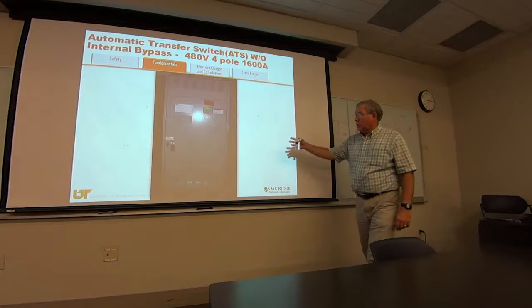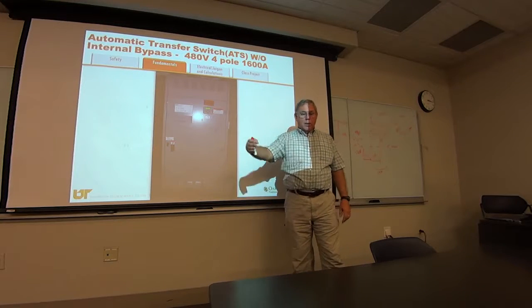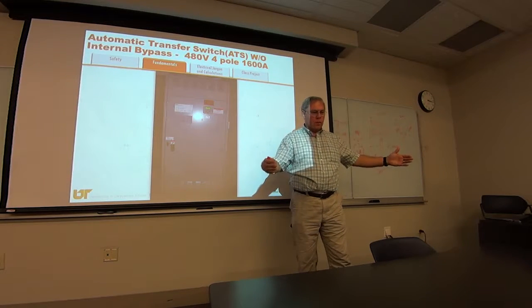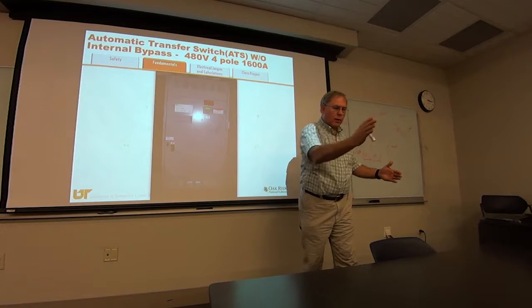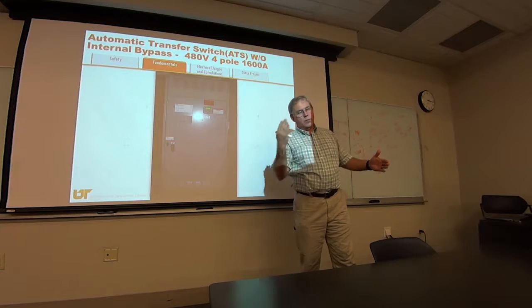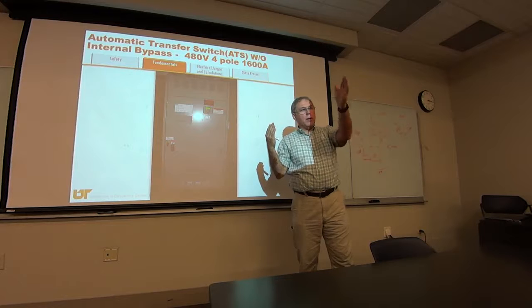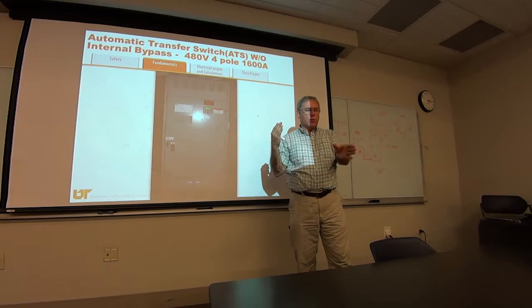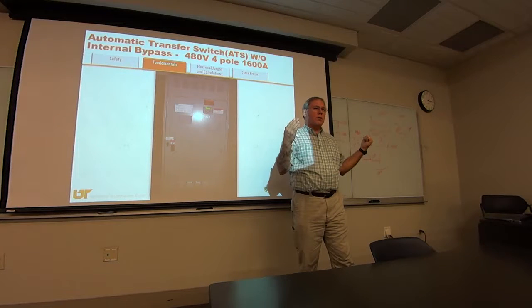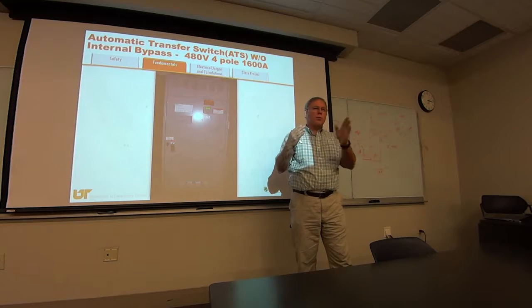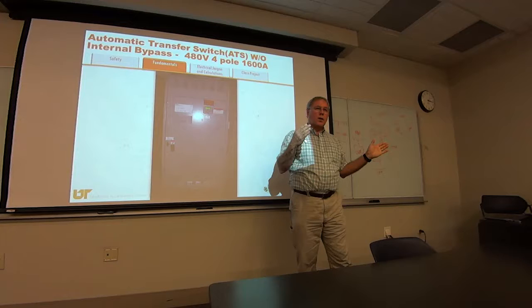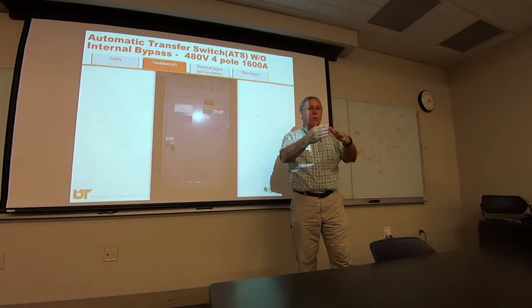This is a transfer switch. You got a UPS and you got a generator and you got normal power. Normal power comes into the transfer switch and is normally feeding the UPS. If normal power drops off, this transfer switch will say, hey, I've lost power, and it'll tell the generator to start, and as soon as it's running, it'll transfer the UPS over to the generator. Then when normal power comes back on, it'll transfer it back.